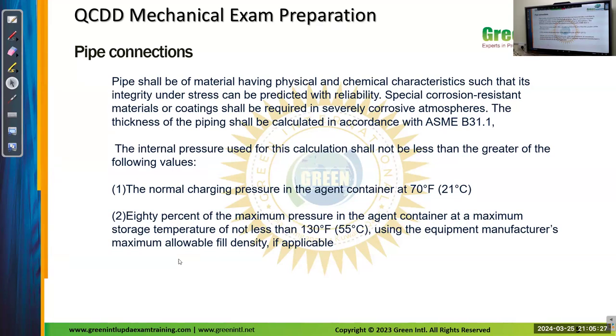The thickness of the pipe shall be calculated in accordance with ASME B31.1. Internal pressure used for this calculation shall not be less than the greater of the values: normal charging pressure of the agent at 21 degrees Celsius, or 80% of the maximum pressure of the agent container at maximum storage temperature of not less than 55 degrees Celsius using the equipment manufacturer's allowable fill density, if applicable. So internal pressure will be calculated based on these conditions, and we will take the greater of these. Okay.